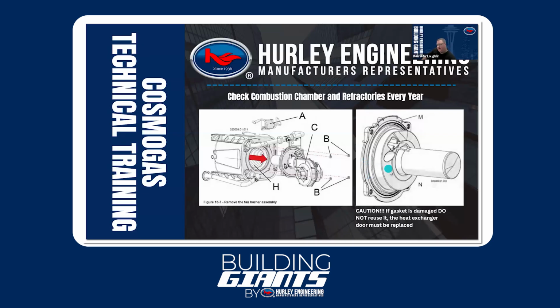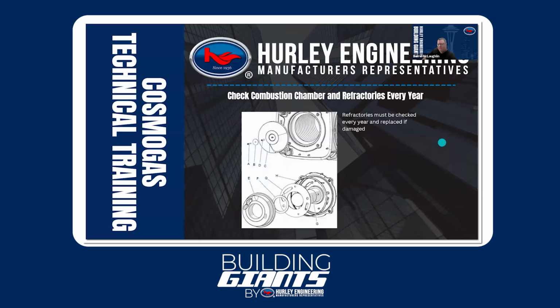So it's vital that whenever you're doing annual maintenance, you're going to be looking at the fire sides anyway. Let's pull these out and make sure there's no cracks, make sure they're in good shape, and replace them if necessary. So now this is the front refractory by the mesh burner. But when we pull it out, we've also got a rear target wall that will bolt to the back of the heat exchanger. And that one should be inspected and replaced as needed as well. So at least once a year. And once a year is a good thing for heating systems.